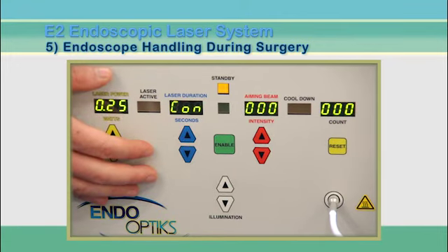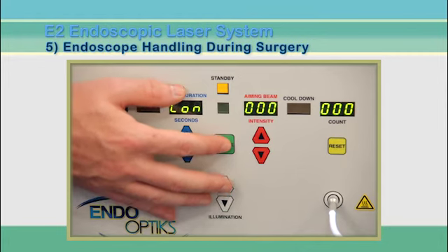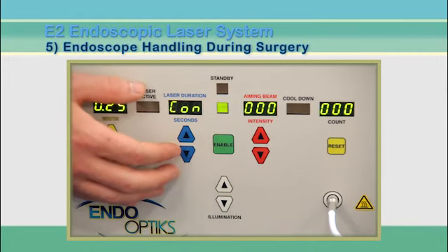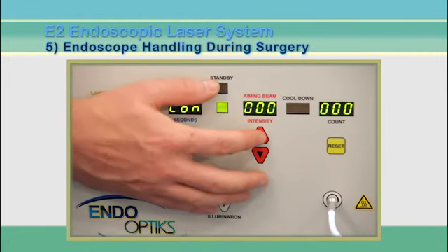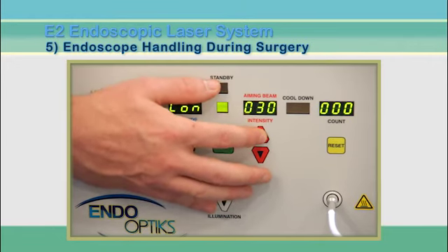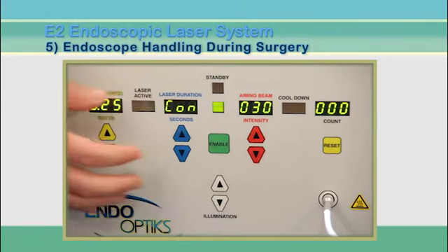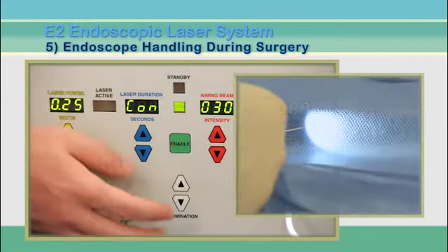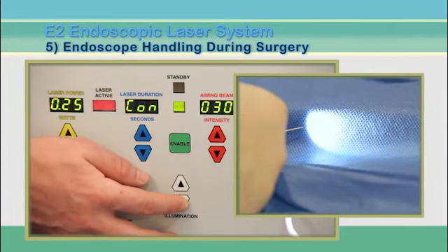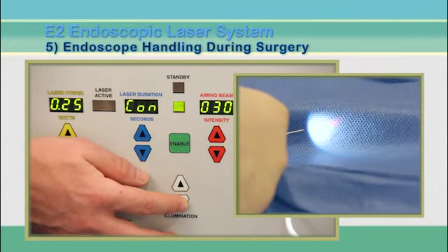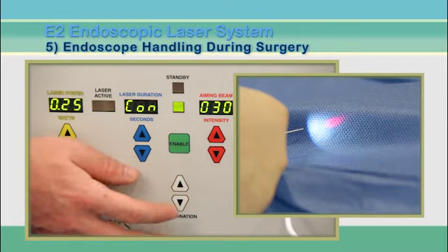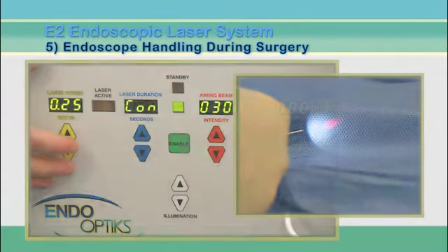When the surgeon is ready for the endoscope, you should press the green enable button to activate the laser. Then press the up arrow for the laser aiming beam 2 or 3 times to get the 20 or 30 setting. When the white light is reduced, the laser aiming beam should be clearly visible on the screen as a small red dot or donut, and you will see the red glow from the tip of the cannula.